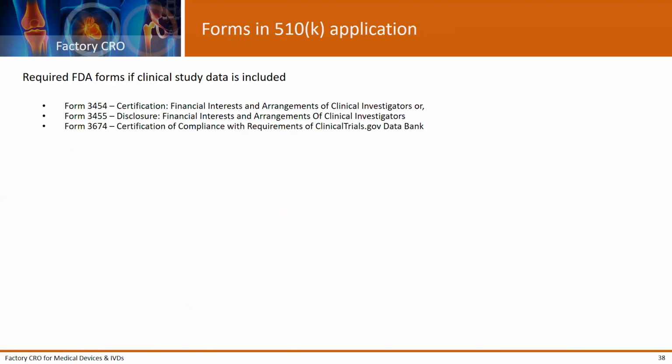There are a few forms that are applicable if you file a 510(k) application that come with clinical studies: the financial disclosure of financial interests of your clinical investigators, and a certification of compliance with registration on clinicaltrials.gov before you actually start executing your clinical investigation.